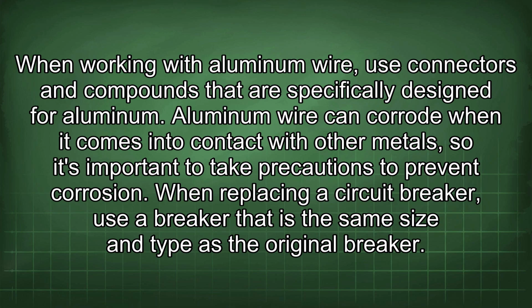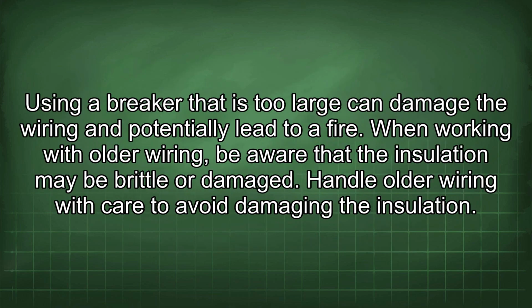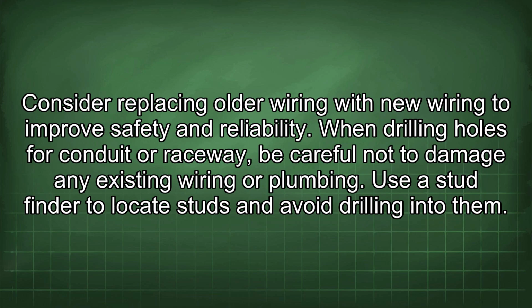When replacing a circuit breaker, use a breaker that is the same size and type as the original breaker. Using a breaker that is too large can damage the wiring and potentially lead to a fire. When working with older wiring, be aware that the insulation may be brittle or damaged. Handle older wiring with care to avoid damaging the insulation. Consider replacing older wiring with new wiring to improve safety and reliability.